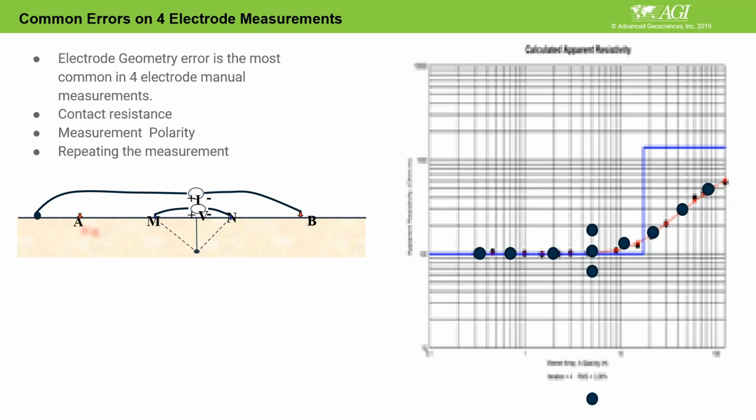So this is a typical error, because sometimes you say, okay, go to the next point. Even if your cable is marked or the ground is marked, it's difficult to mark the ground, but typically what you do is you mark a cable and then you come up to that next point. If one of these operators mixes it up, and very often they do, then instead of staying over here, they stay there, but you never know. And then you just push your button, you measure, and you get your measurement. That means it doesn't show any error on your measurement.